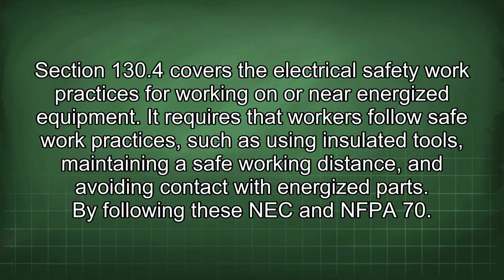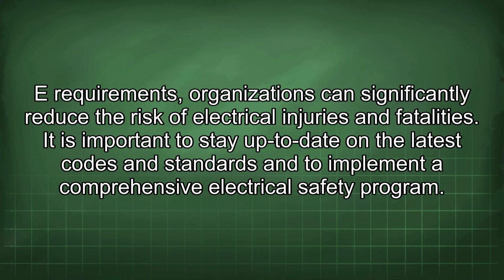Section 130.4 covers the electrical safety work practices for working on or near energized equipment. It requires that workers follow safe work practices such as using insulated tools, maintaining a safe working distance, and avoiding contact with energized parts. By following these NEC and NFPA 70 requirements, organizations can significantly reduce the risk of electrical injuries and fatalities. It is important to stay up to date on the latest codes and standards and to implement a comprehensive electrical safety program.